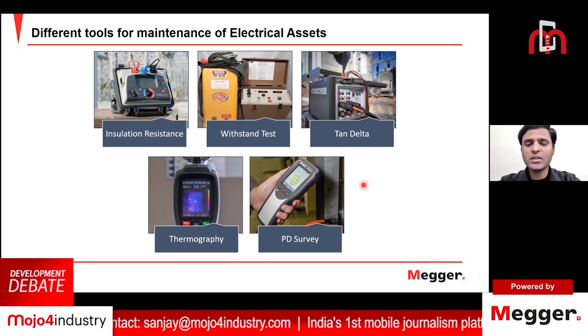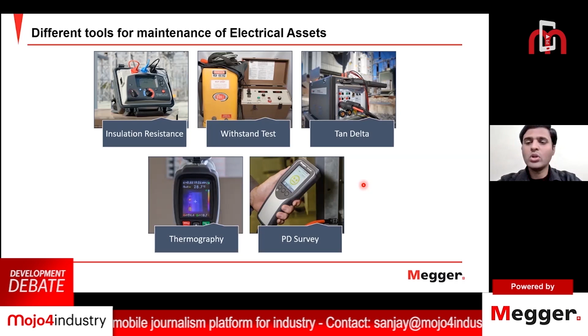So nowadays there is a trend of using partial discharge surveys on electrical assets, which help you detect discharges in online conditions. From the outside of the panel, you detect the different types of discharges emitted from the internal components of your electrical assets, like medium voltage switchgear panels or transformers. The PD survey is a new tool that has come into the market and is very well accepted. Many industries are looking forward to using this survey tool for predictive maintenance and to understand the condition of the electrical asset. Thank you so much.